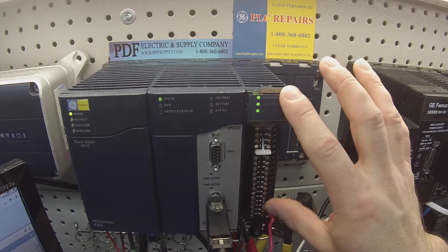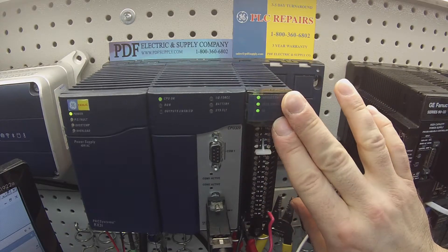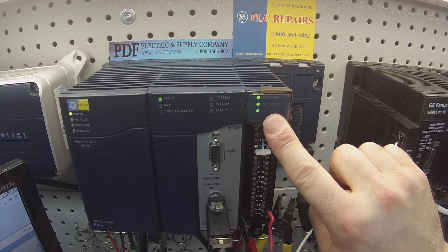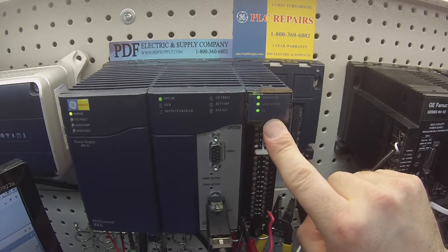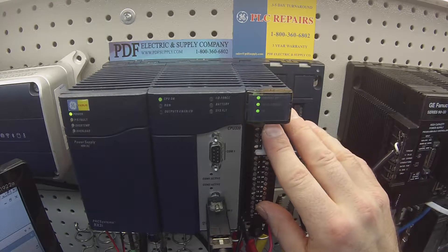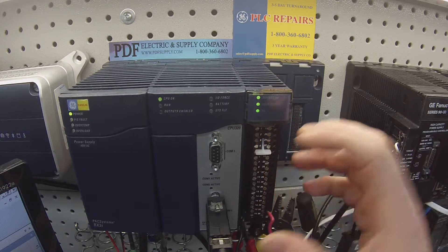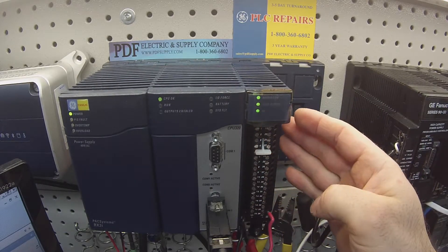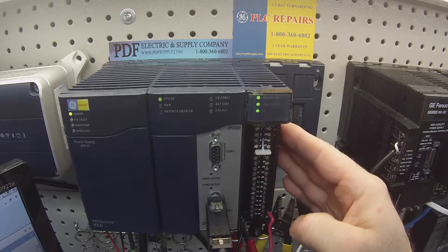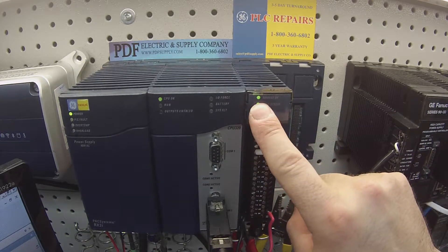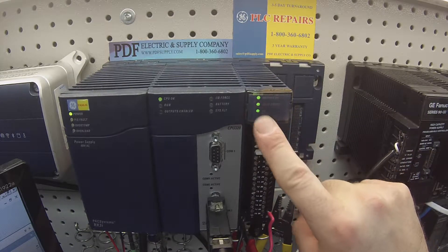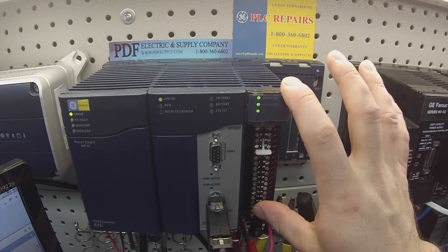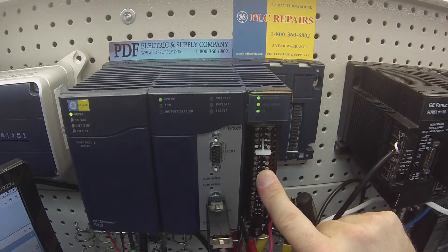So this is exactly what you guys should have going into the test is a light pattern that looks like this. If you don't, then it's likely that it's unable to take the power of the 24 volt DC because there's an issue with the card or if you don't have a module OK light or any of these lights are not on, then it's immediately a failed card.